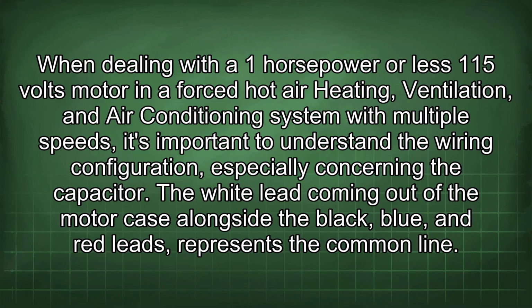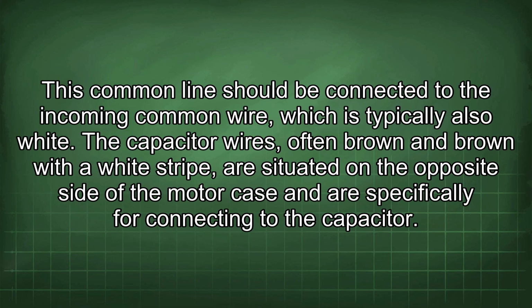When dealing with a 1 horsepower or less 115 volts motor in a forced hot air heating, ventilation, and air conditioning system with multiple speeds, it's important to understand the wiring configuration, especially concerning the capacitor. The white lead coming out of the motor case alongside the black, blue, and red leads represents the common line. This common line should be connected to the incoming common wire, which is typically also white.